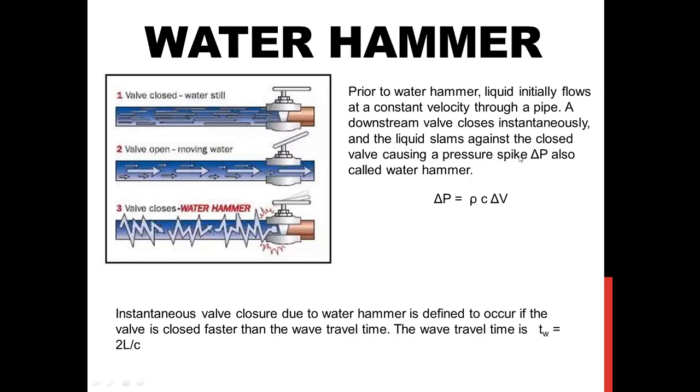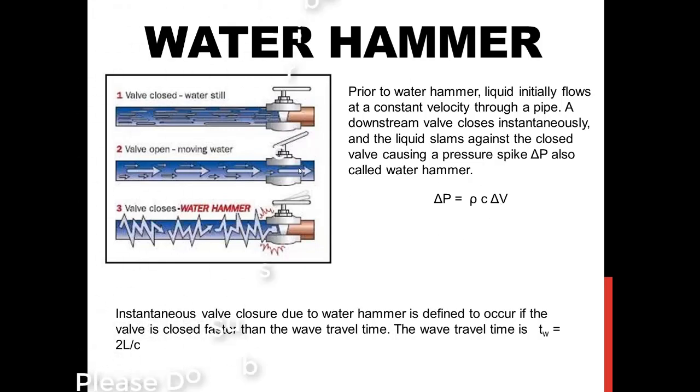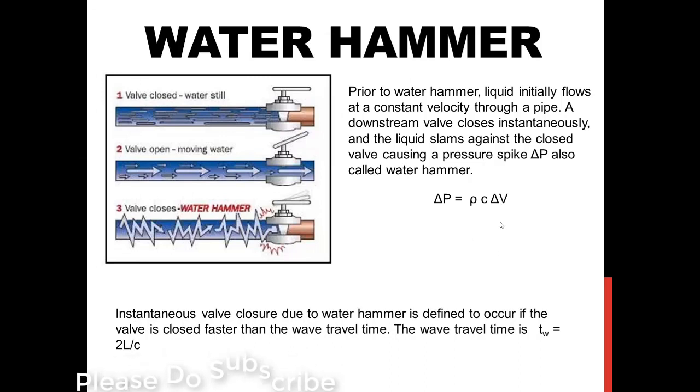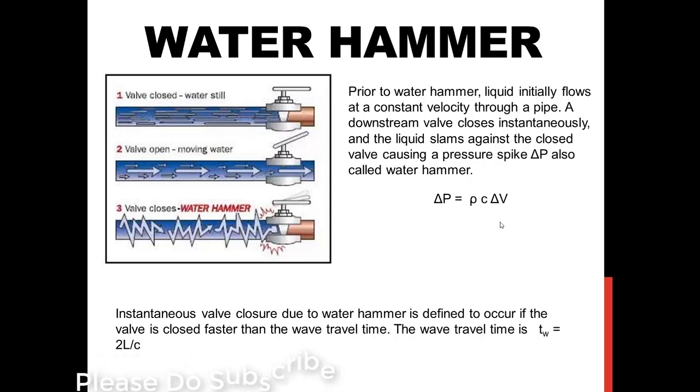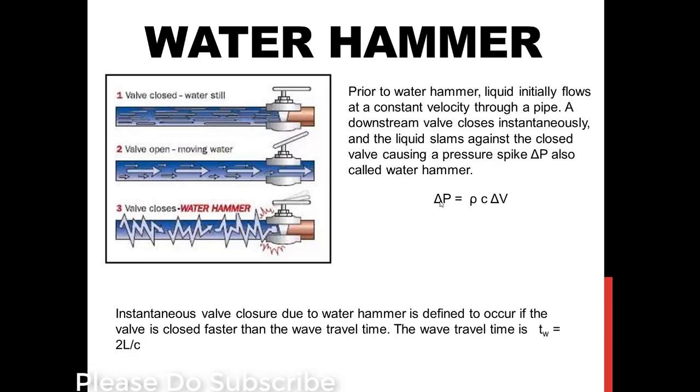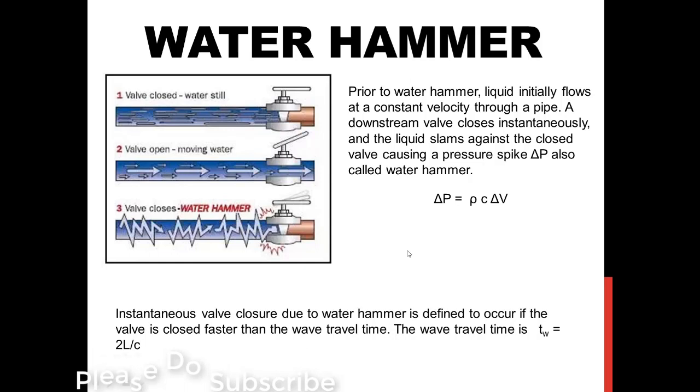That wave is formed due to that sudden pressure rise. The sudden pressure rise or spike is called water hammer and it is derived as delta P equals rho into C into delta V. C is the velocity of sound and delta V is a sudden change in velocity from initially constant to zero. It can be three or four or five meters per second. Delta P is that current pressure spike and delta V is the change in velocity.